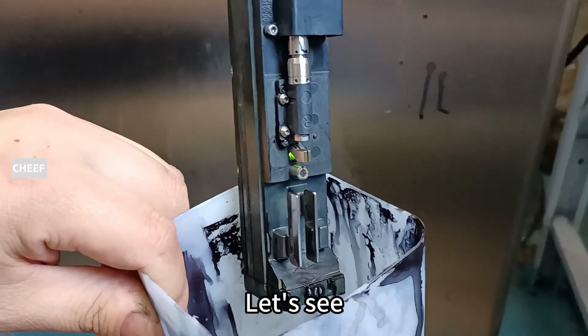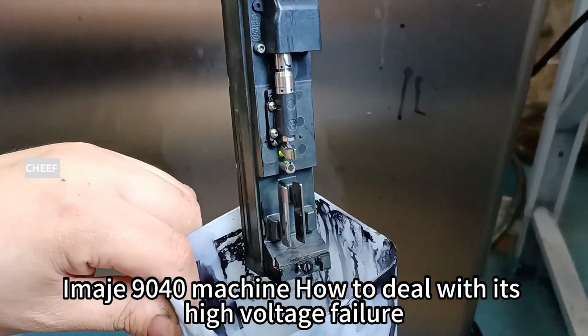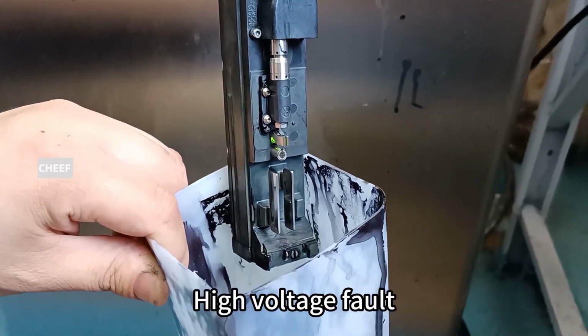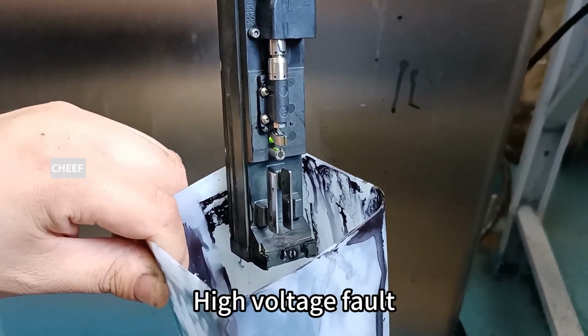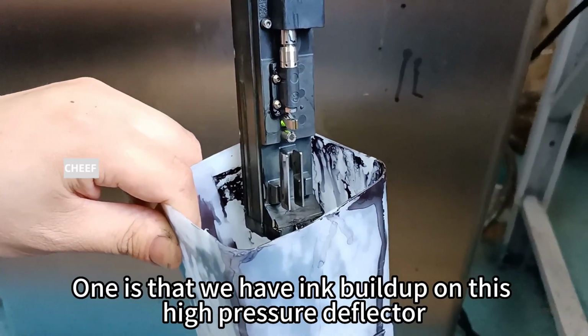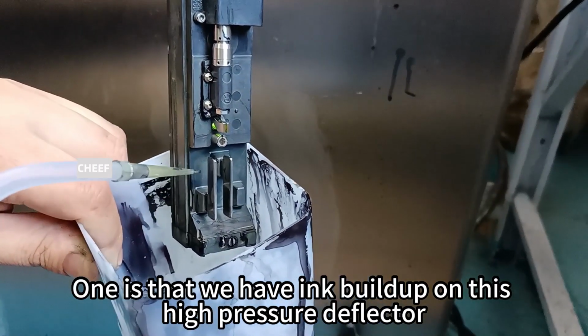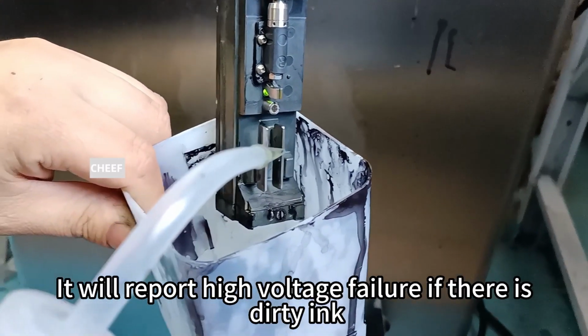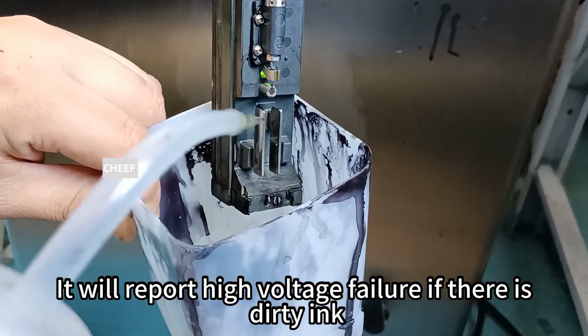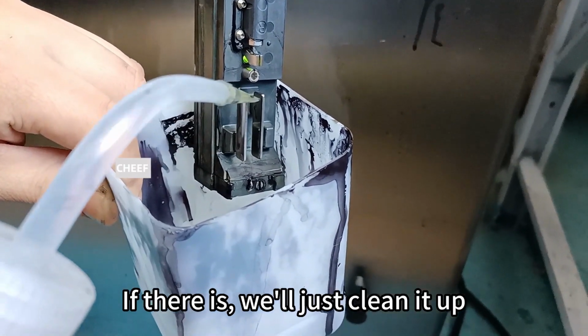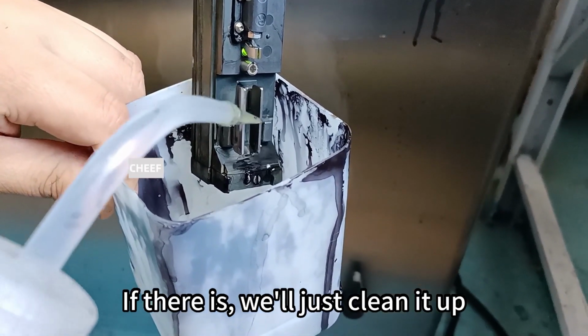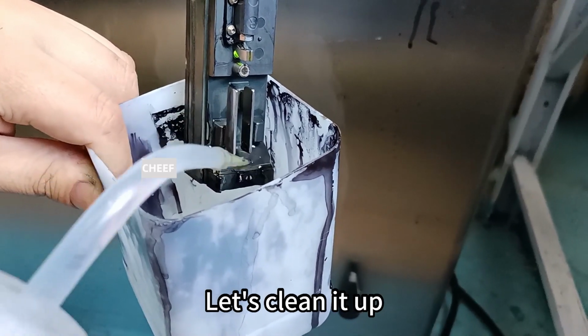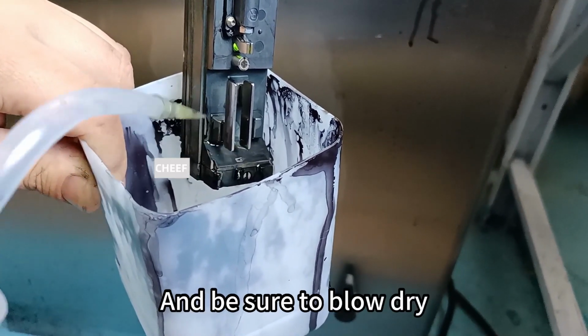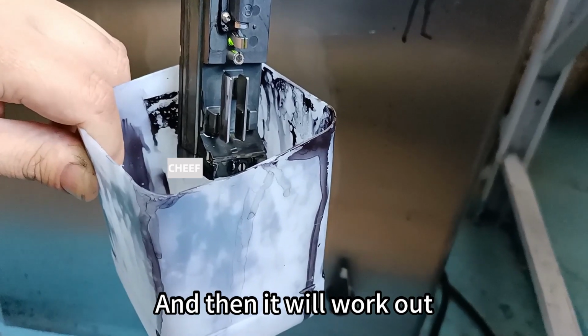Let's see how to deal with the high voltage failure, the high voltage fault, on the Imaje 9040. There are a couple of things. One is that we have ink buildup on this high pressure deflector. It will report high voltage failure if there is dirty ink. If there is, we'll just clean it up. Clean it up, and be sure to blow dry, and then it will work.